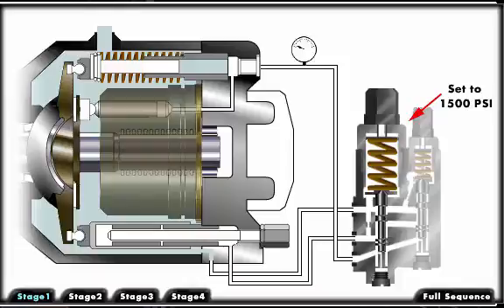Variable volume pumps can also be pressure compensated. A pressure compensated piston pump de-strokes or moves to zero output at a predetermined pressure. This is accomplished by hydraulically positioning the pumping chambers to zero output while maintaining compensator pressure at the outlet of the pump.